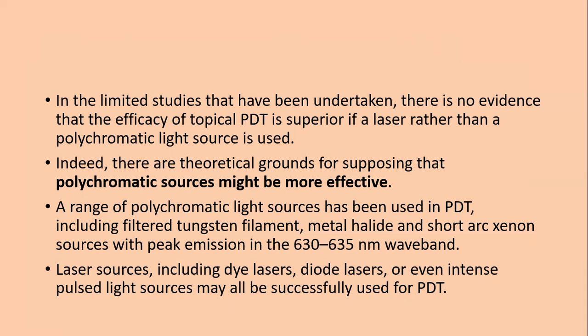A range of polychromatic light sources has been used in PDT, including filtered tungsten filaments, metal halides, and short arc xenon sources with peak emission between 630 to 635 nm. Laser sources including dye lasers, pulsed dye laser, diode laser, and even IPL may be successfully used as alternates.